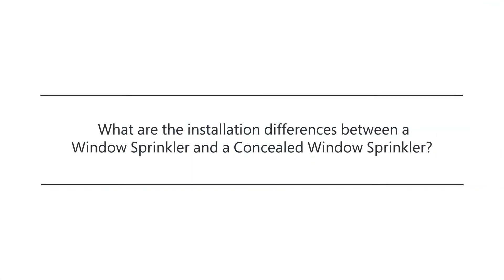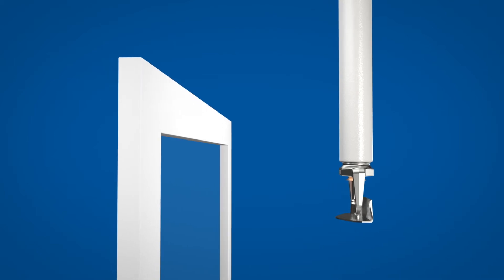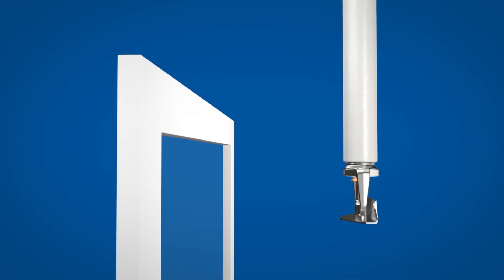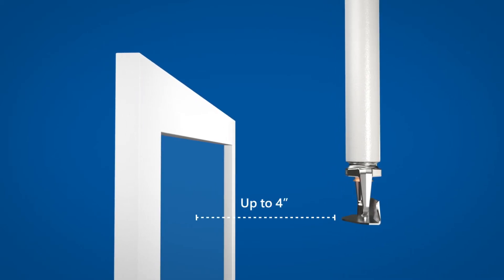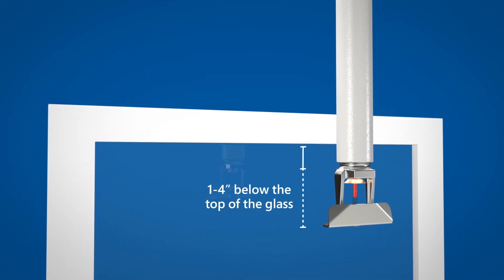What are the installation differences between a window sprinkler and a concealed window sprinkler? Exposed window sprinklers are designed to be installed directly in front of the glass, up to four inches away. This sprinkler sits one to four inches below the top of the glass.